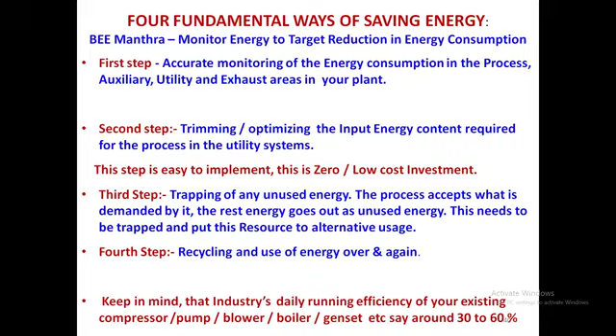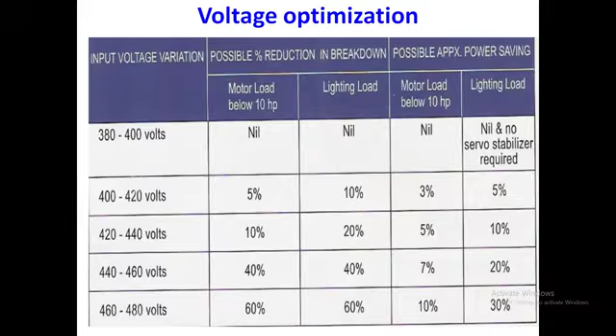What I was telling you before, this is the case study where it shows, and we have seen it in many of the industries. When operating at 400 volts versus 440 volts, there are around 10% savings, around 5% savings on the motor. For lighting, especially the previous HID type lightings, it was around 10%, but for LED now it's around 5% only. High intensity discharge and fluorescent tube lights had a lot of savings, but LED also gives savings of around 5%. This we have seen through our case studies in our industry.